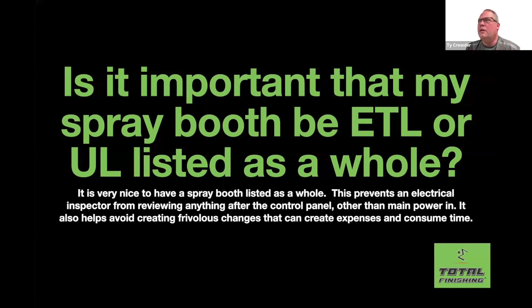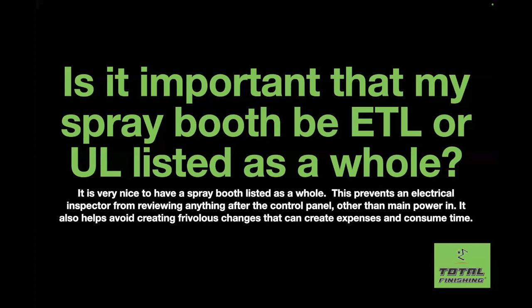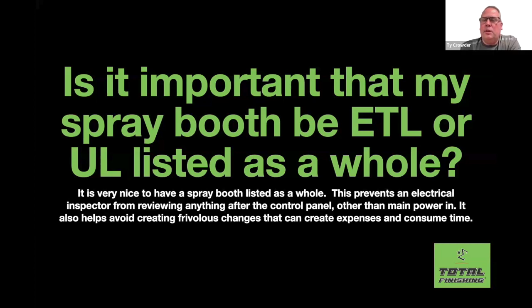I didn't like the gauge of wire. I like it in some kind of different conduit. I like a sticker over here. You know, they come up with all kinds of things. I've seen it where they had a customer have to pay for third-party listing because they don't want the liability of inspecting it. And that's a whole new thing that's going on out there now. So having a booth arrive that's completely ETL or UL listed just stops problems.